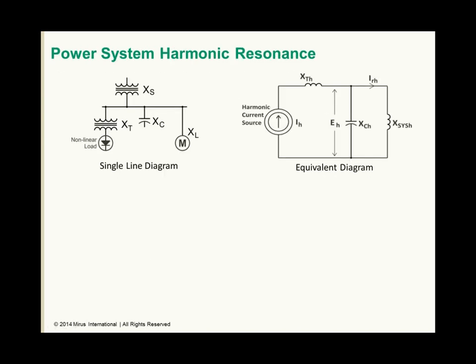Power system harmonic resonance results when the current introduced by the harmonic generating loads is subjected to a power system where the capacitive reactance is equal to the inductive reactance at a certain harmonic frequency. This simple single line diagram has a source and a source reactance, XS. We have a nonlinear load, which could be a variable speed drive, injecting harmonics into the power system. These harmonics pass through, say, a transformer and its impedance into the bus where we have power factor correction capacitors connected in parallel. And then we also have all of our other loads in the system, which might be fixed speed motors that have an inductive reactive component.